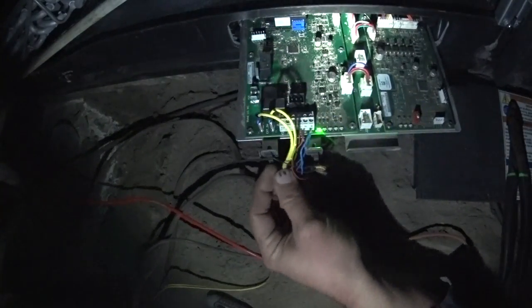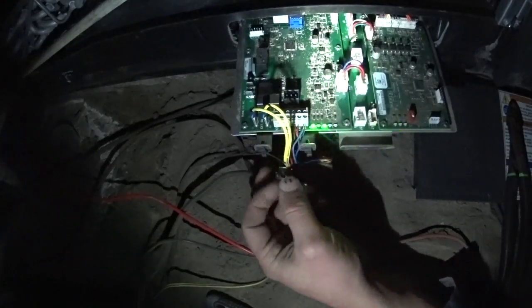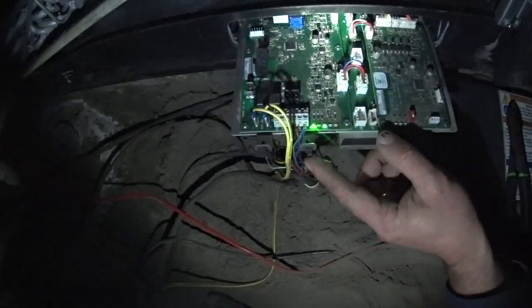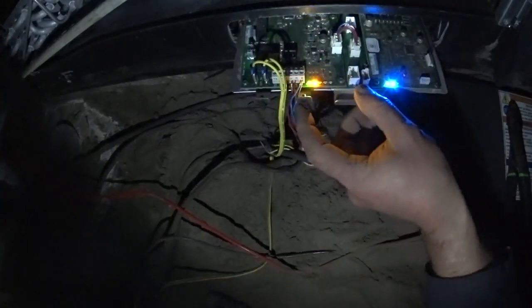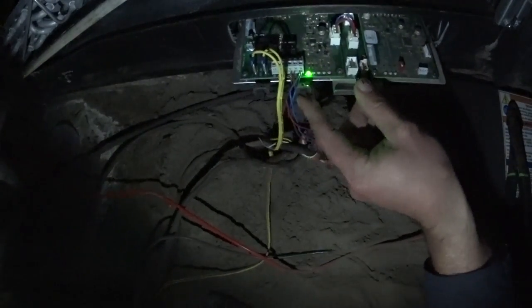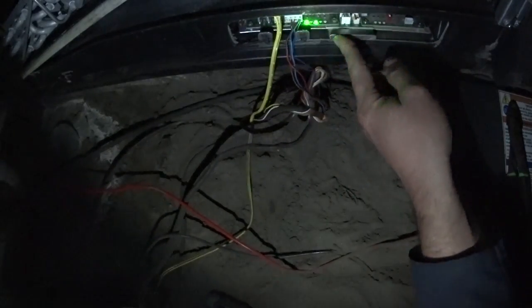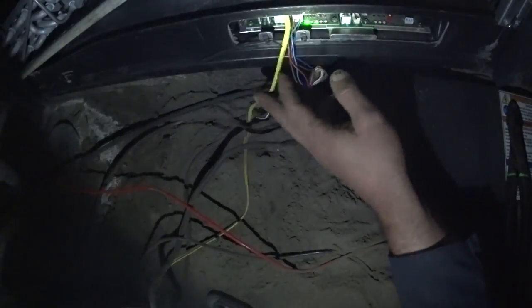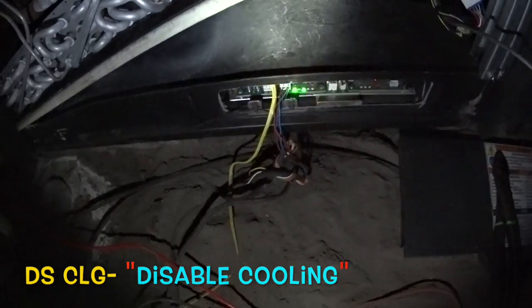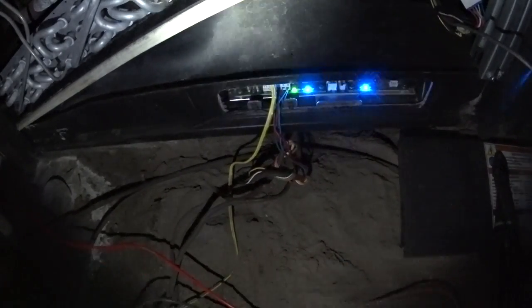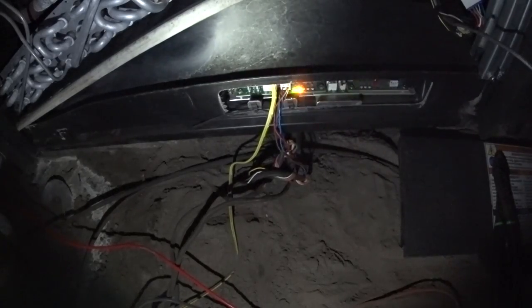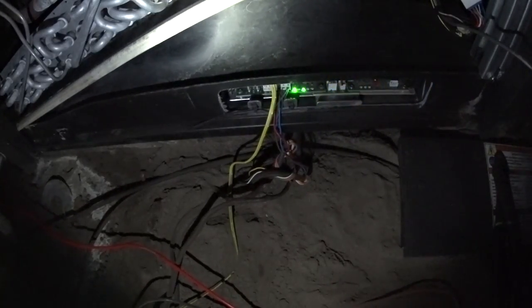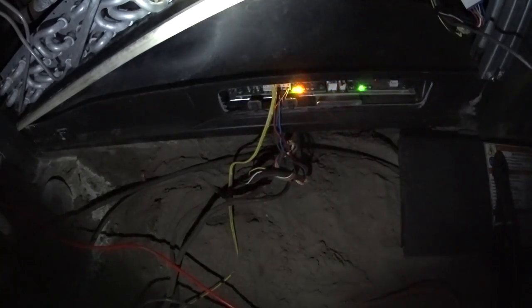it will tell you on the user interface or thermostat that you have a fault on that switch, and you can set up the thermostat to recognize different items on the switch connections. So in this particular instance, we are going to set that up for disabling cooling if that switch is engaged, or broken I should say. It is normally closed and open on water level rise.